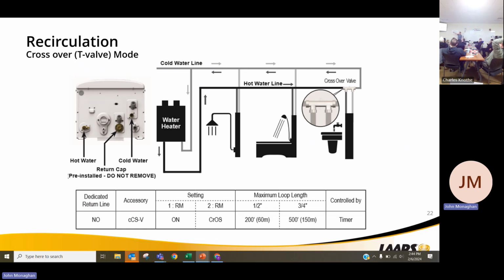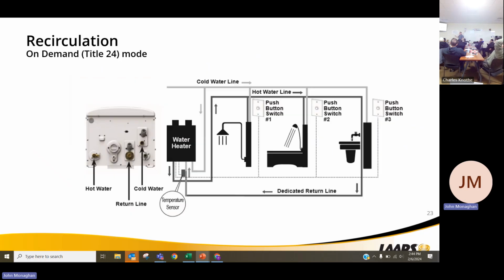This is where we would have our crossover fitting at the end of the unit. We're going to have to set the programming for cross. Tell it that we're doing a crossover, then do it by a timer. Run it for 20 minutes on, 40 minutes off, 10 minutes on, 50 minutes off, and so on and so on. So it's not set for constant recirc.